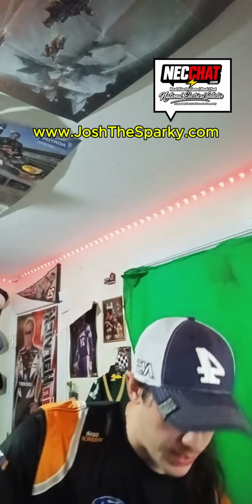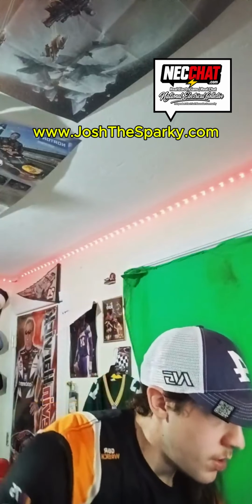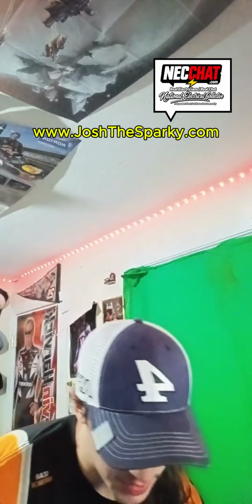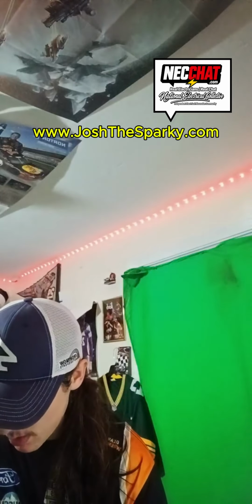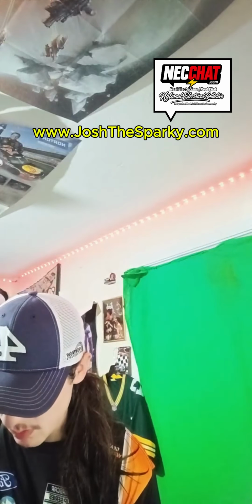So, we are going to go ahead and take our 30 amps. We've got to basically sum these. We've got to see which one is the minimum. So we're looking for minimum, and we are using 1.25. Okay. We're going to take our 30 amp and 24 amp, right? We're going to take 30 amp times 1.25, 24 amp times 1.25.